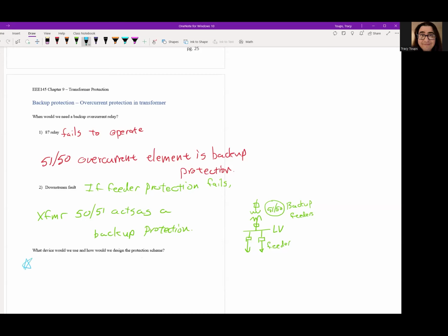So you definitely want, in the star, this is pretty much mandatory, some type of high side protection. Typically you have a high side 50-51 relay for the transformer. And honestly, you really should have this. But if you are absolutely cheap and not willing to spend a dime, you can technically use a fuse if you want, but I'm not a big fan of it because once a fuse blows, you have to go replace it. It's much better if you use a 50-51 for the transformer, but I'm going to put fuse in parentheses, maybe. I would not suggest it, but I've seen it in the field like this, especially in old designs.